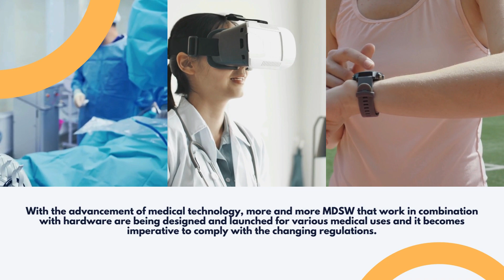The manufacturer must implement adequate controls to monitor the hardware's proper function and mitigate any identified risks. This ensures that the medical device software, when used with the hardware components, remains safe and effective. This includes assessing and controlling risks from hardware malfunctions and use errors, and applying inherent safety measures by design. With the advancement of medical technology, more and more medical device software that work in combination with hardware are being designed and launched for various medical uses, and it becomes imperative to comply with the changing regulations.